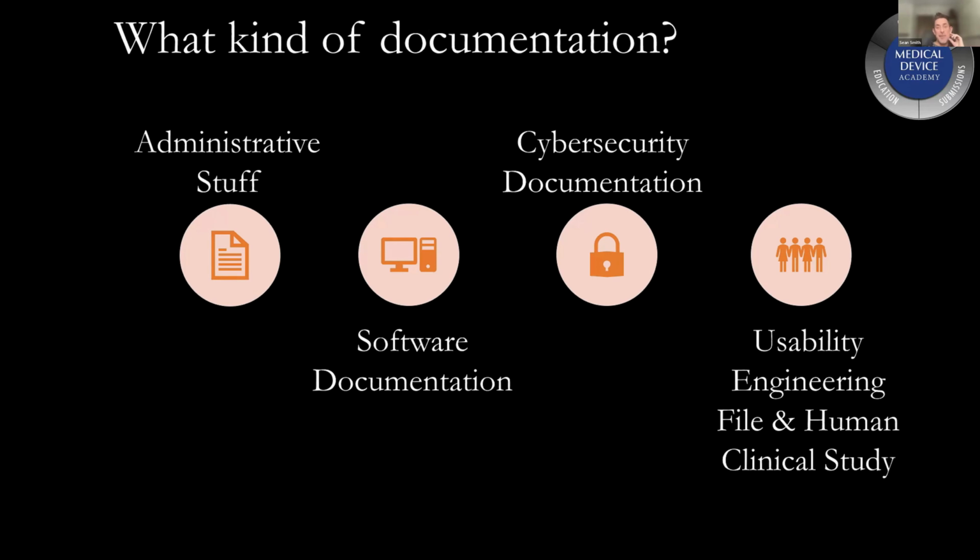So here's a question. Can you speak on auditing software as medical devices that don't reference any standards for cybersecurity? I've seen software as medical device developers claiming compliance only to ISO 13485, ISO 14971, and IEC 62304. Yep. So you can have software that doesn't claim compliance with any standard.